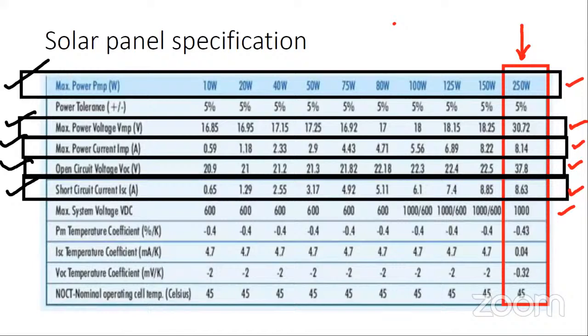So now we are checking the data sheet of the PV module first. Then subsequently we will see the PV inverter data sheet also. We will be considering a few factors and we will check whether those limits are exceeding the limit or within the limit.